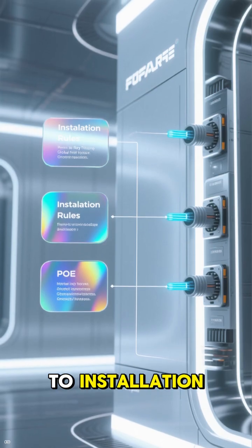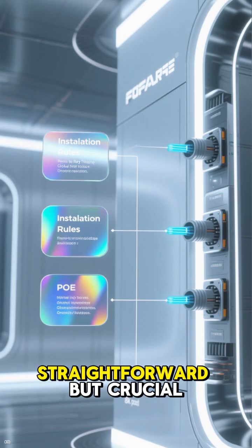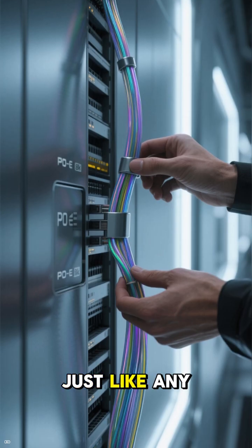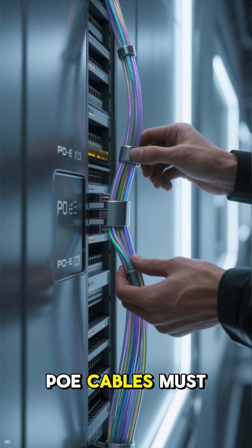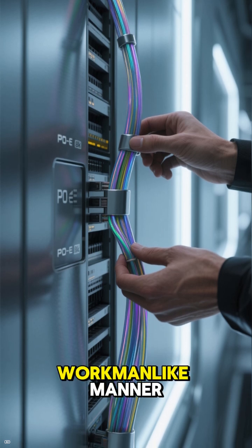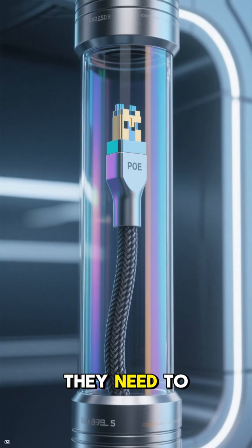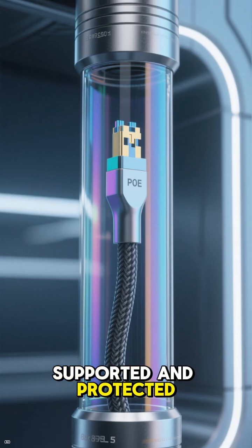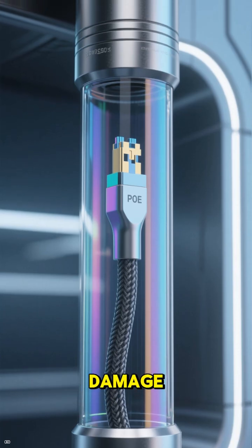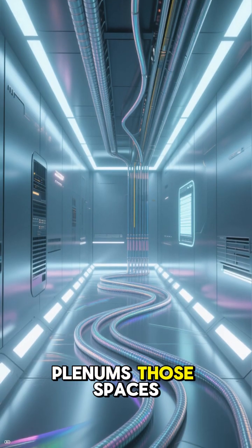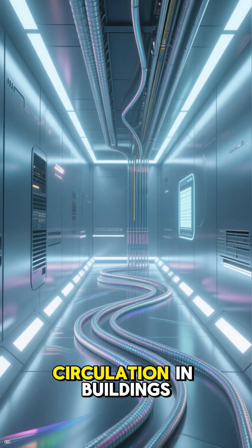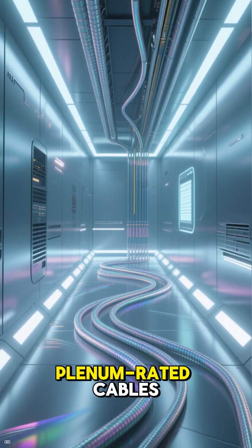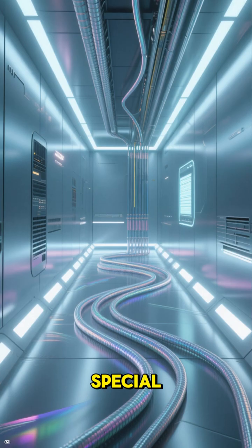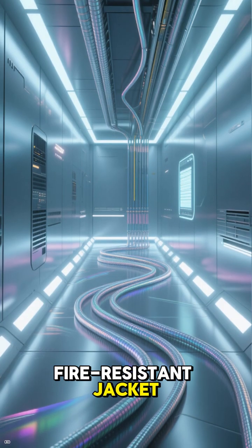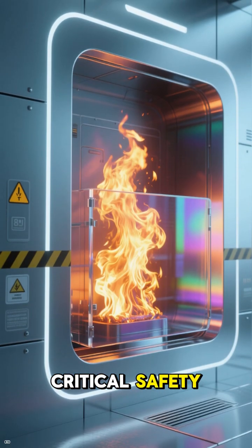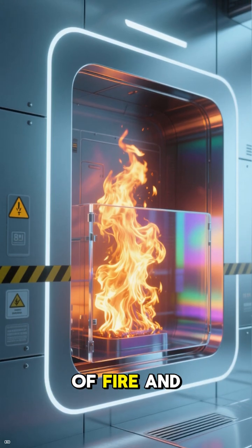When it comes to installation, the rules are pretty straightforward but crucial. Just like any other wiring, PoE cables must be installed in a neat and workmanlike manner. They need to be properly supported and protected from any physical damage. If you're running them through plenums, those spaces used for air circulation in buildings, you must use plenum-rated cables, which have a special fire-resistant jacket. This is a critical safety measure to prevent the spread of fire and smoke.